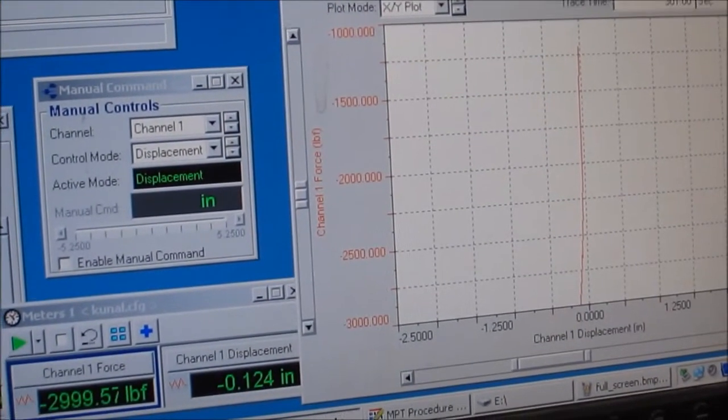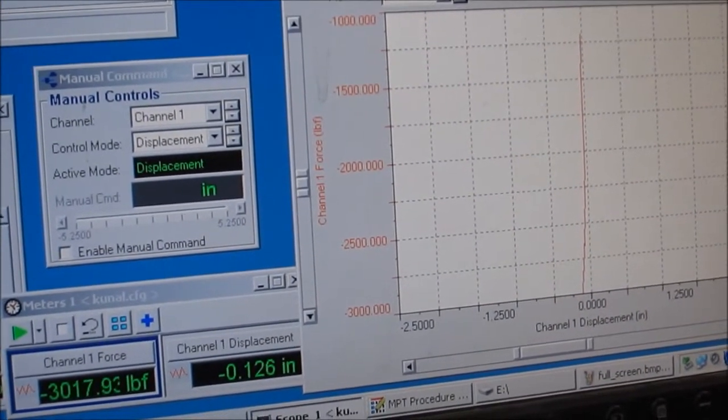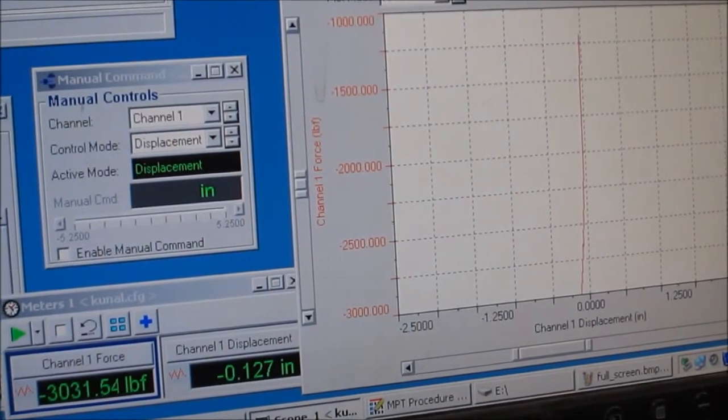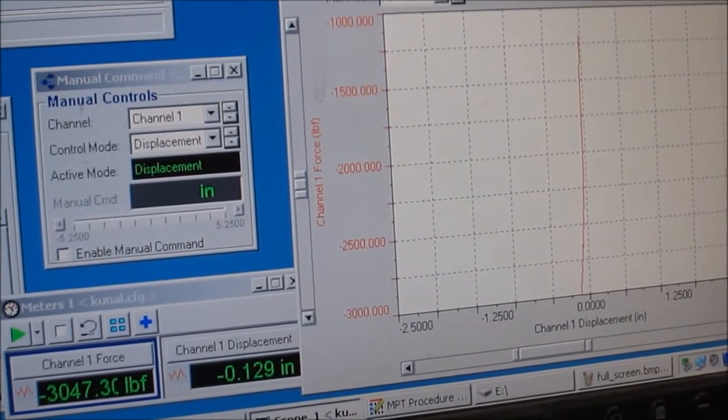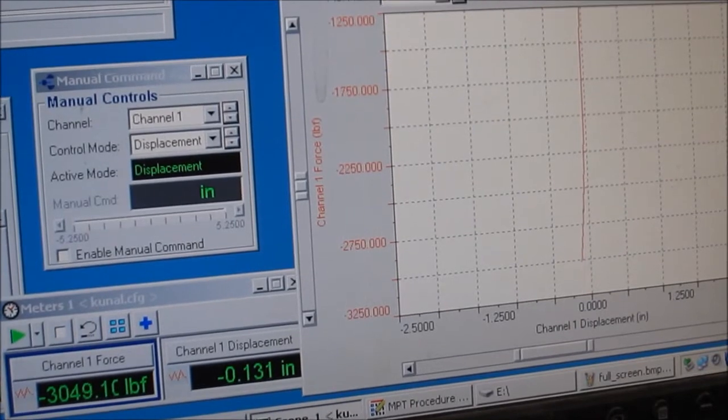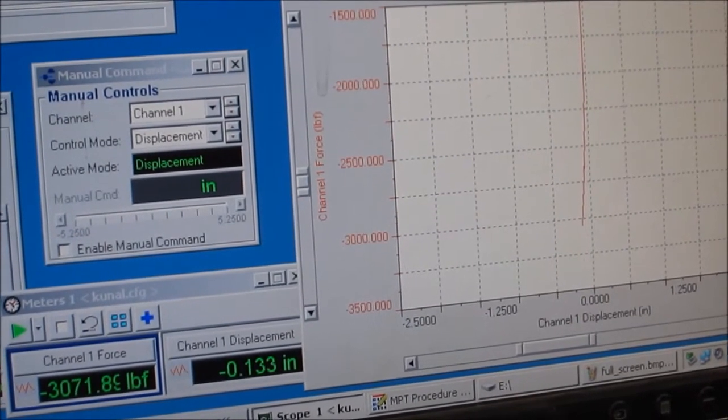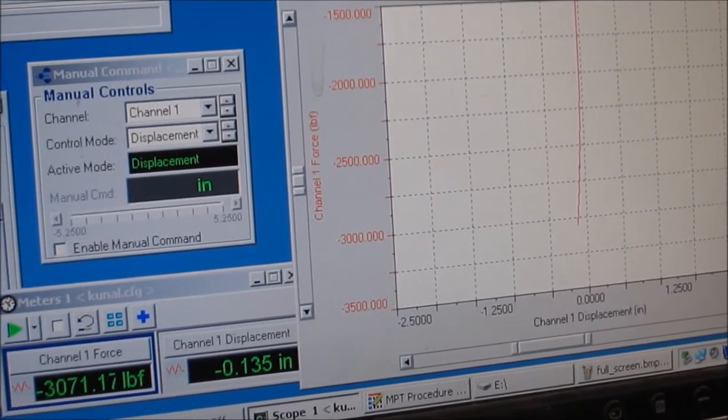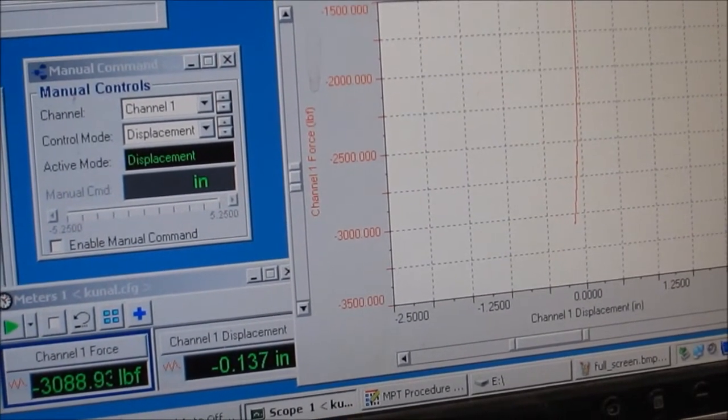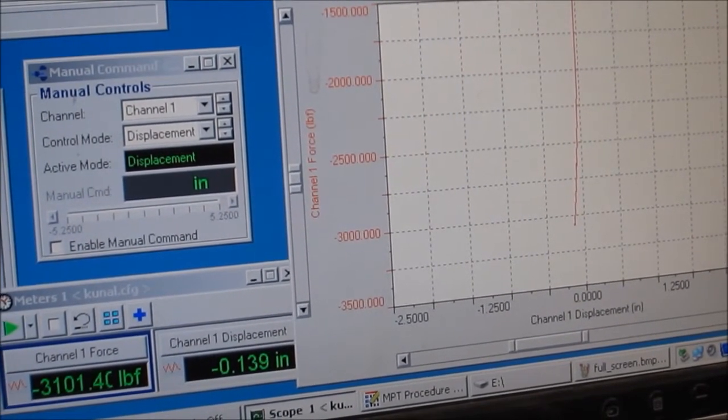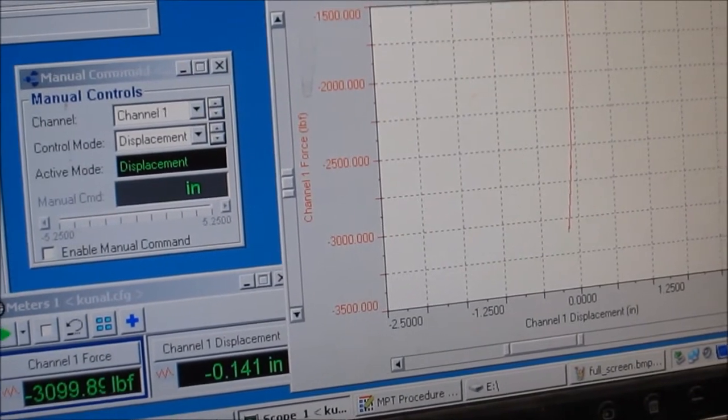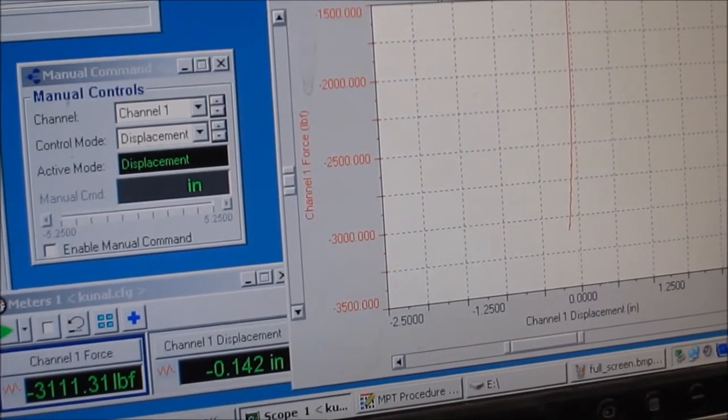By moving around the offset scaling buttons and auto offset keys, you can change the size and location of this trace so that you can watch the test as it proceeds. Also notice in the lower left-hand corner you can see real-time output from channel one force and channel one displacement.